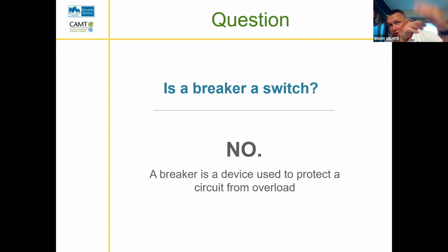Your switch on the wall here is a switch, but if it overamps, it's not going to pop into a neutral position to prevent current from flowing through it, right? That breaker will. So that breaker is not a switch. It's actually a safety. It's a device used to protect a circuit from overload. Again, this will be on your test.